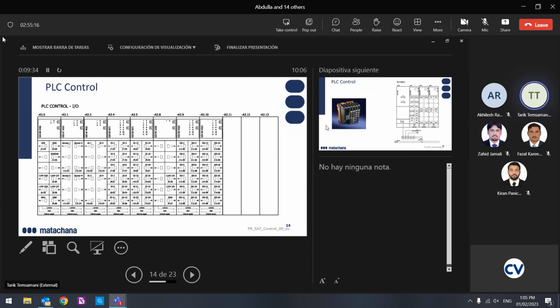If you have to change a module to check if it is working or not, you can change it only by one that has the same number. If not, it's not correct. For example, for the digital inputs, I can exchange R3.4 by R3.5. For the digital output, the same, but I cannot change the R3.9 by another one. Okay, so it's always important to respect this order.